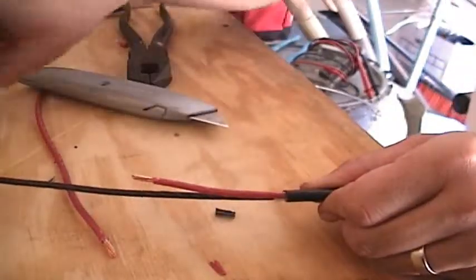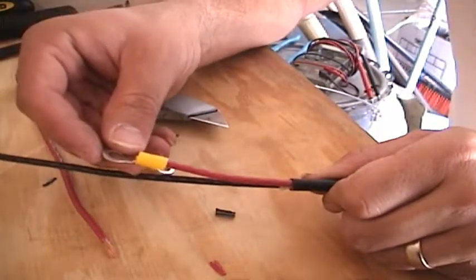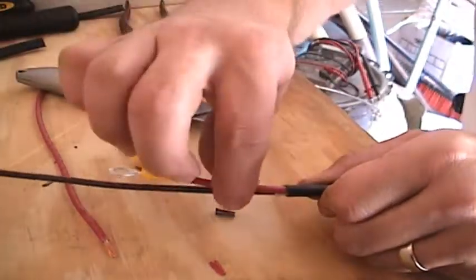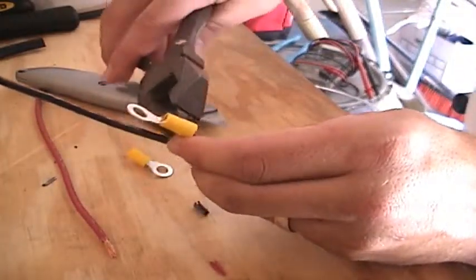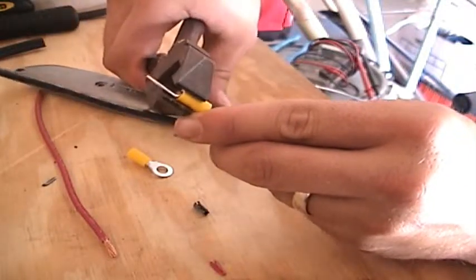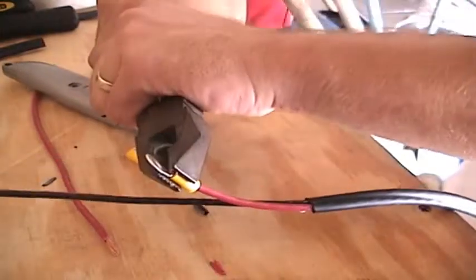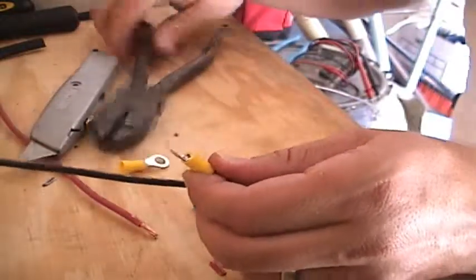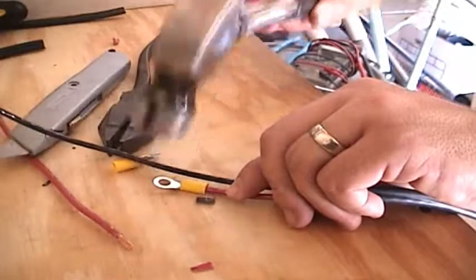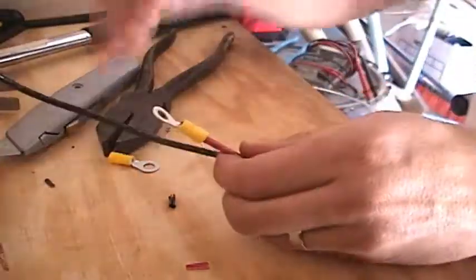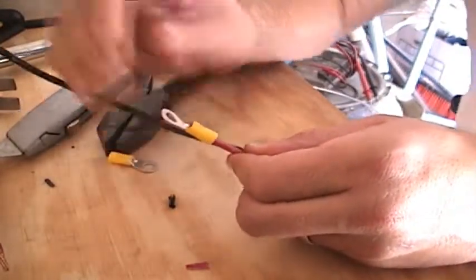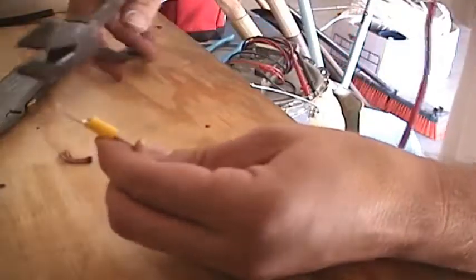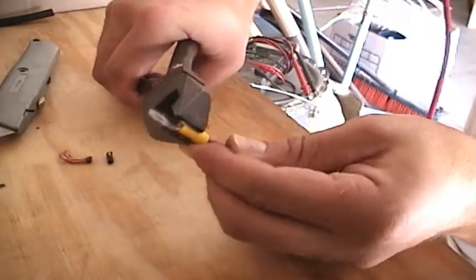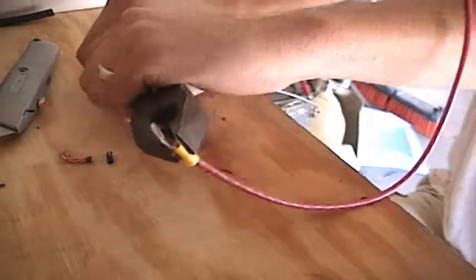Now, using the same ring terminals as before, let's take 2 of them, insert one over the 2-inch piece of red wire coming from the outdoor cable. Go ahead and grab our wire cutters, clamp down nice and tightly. Use the hammer if you'd like. Make sure it's nice and tight. And we'll put the other ring terminal on the 12-inch piece of red wire. Get our wire cutters, clamp down as tight as we can. And then use our hammer.